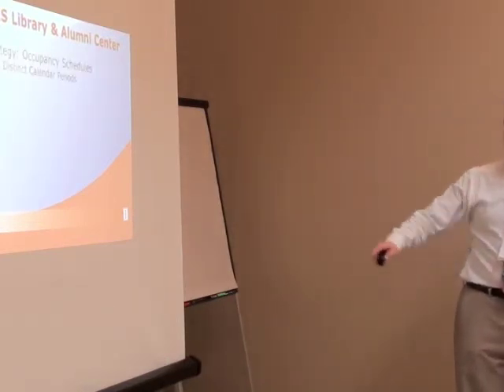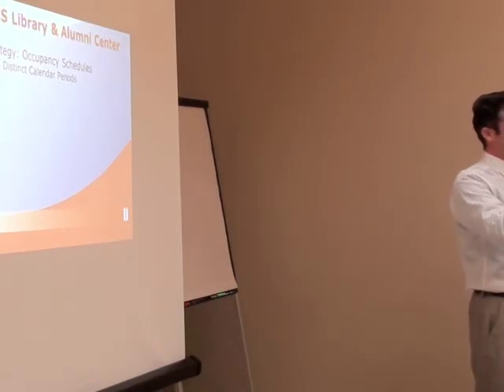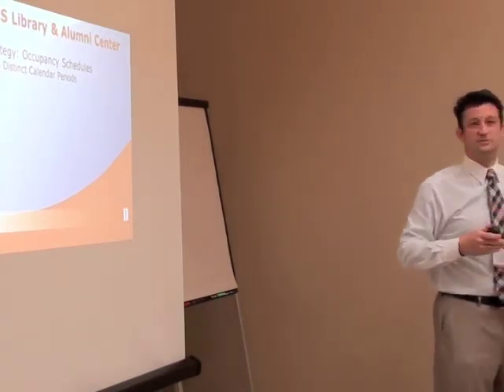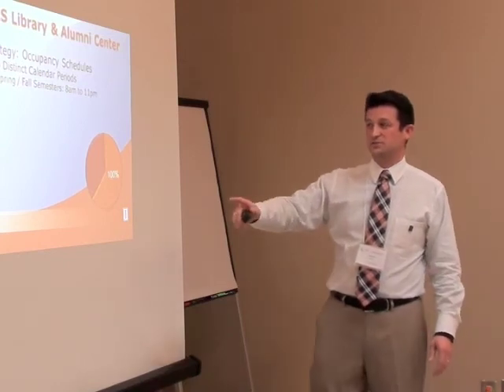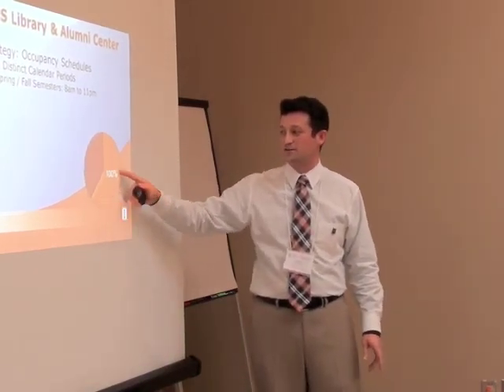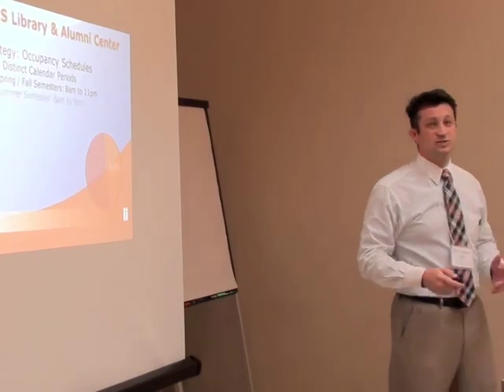So as we went through it, we thought, well, we're going to try to develop occupancy schedules. Ask the people, and we meet weekly with the facility manager to discuss these ideas and bring them to the table. So we had them tell us we need 3 different calendar periods. We need a spring-fall semester when the students are around. So I need you to run or have the air handling unit on for this quantity of time, which is from 8 a.m. to 11 p.m. But in the summer, we could do something different.